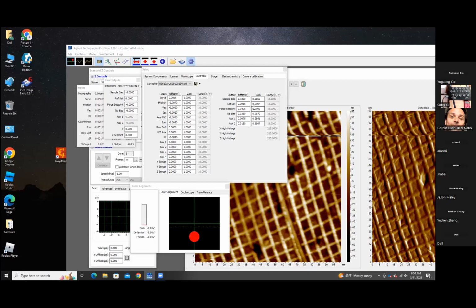And for our operations, basically, we just need to go through the calibration that we can, which is on the breakout box panel, correct? Yeah, so if we want to do KFMs or electrochemistries, make sure the VEC and IEC are well calibrated using this method one at a time. Normally I would remind everybody to save the calibration file with the little save button next to the controller dropdown. But given that this is not the controller that you want to calibrate, I wouldn't recommend saving it. Just close the software and it won't save the changes. So you'll be back to where you were. Okay.